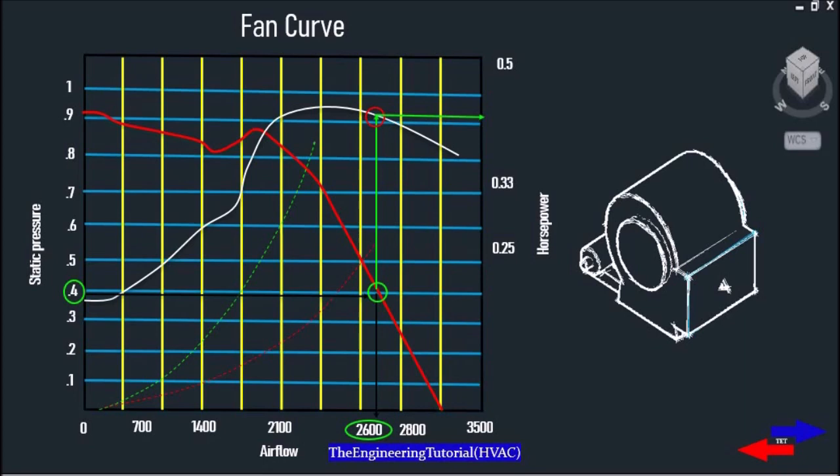and it's operating at a static pressure of 0.4 inches of water column, so it's going to deliver 2600 CFM of airflow. Therefore we have less pressure and more airflow. So as pressure decreases, the airflow increases.